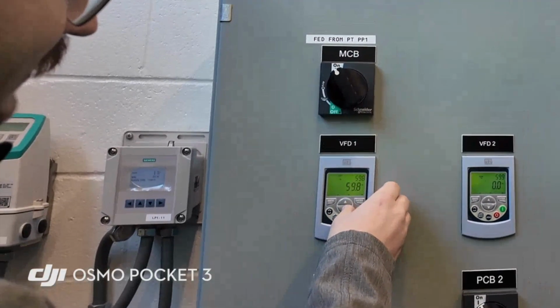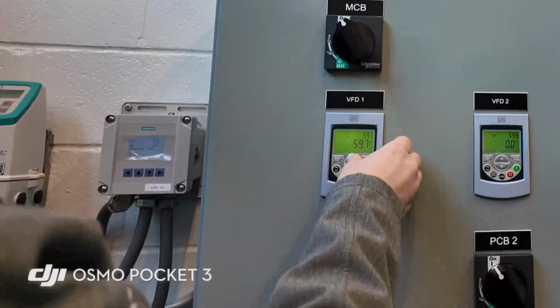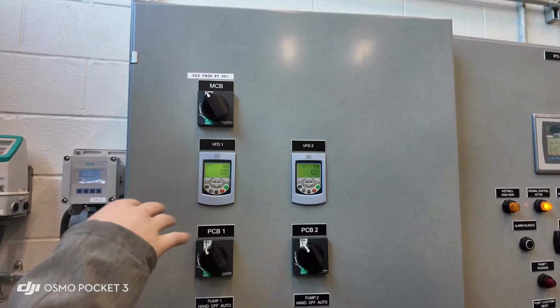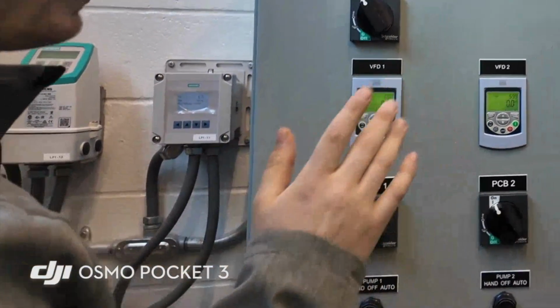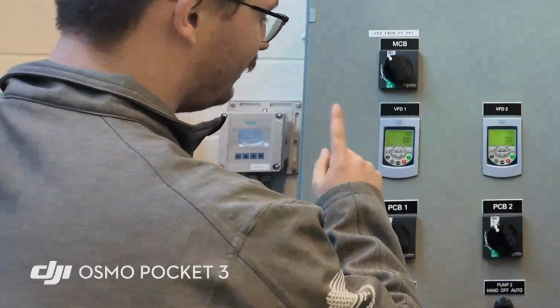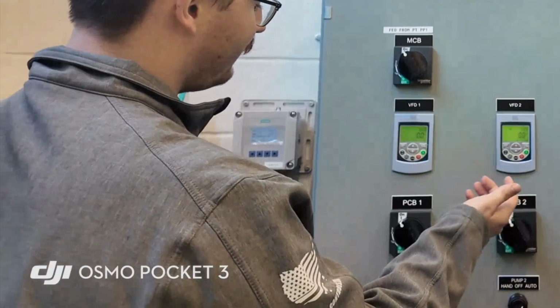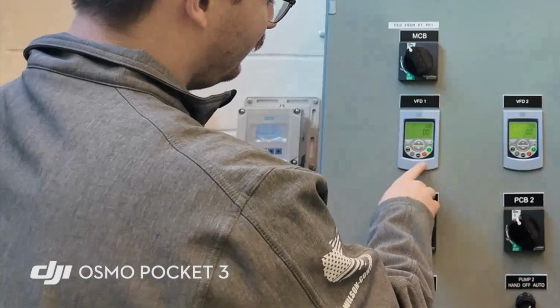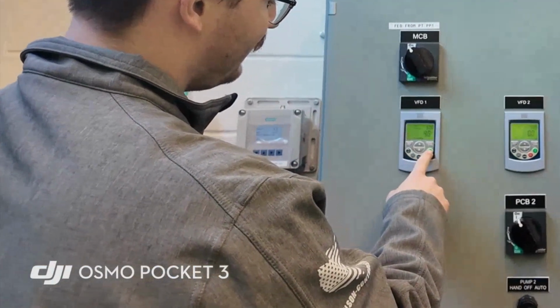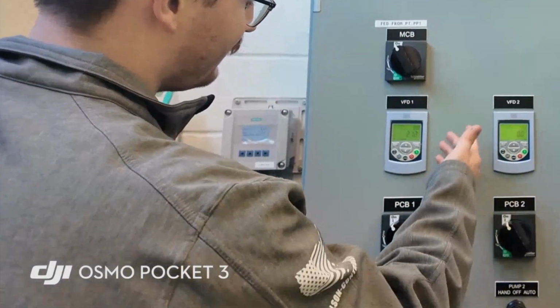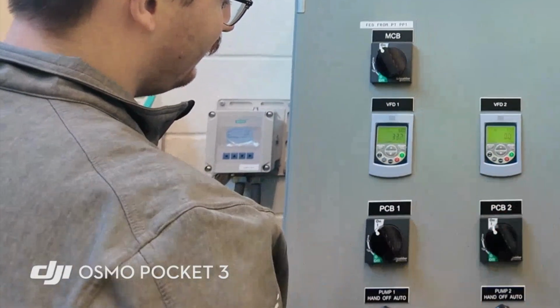60. You can adjust speed using the up and down arrow keys. Max is 60 and its min is 45, so don't go above it, don't go below it. It should have run you to do it anyways. And pretty much once you're in local, you can just hit this green bar. It's going to start to pump out. Once it gets the speed it wants, it'll stop. It's running at full hertz.